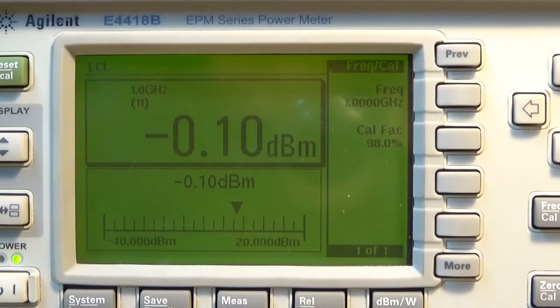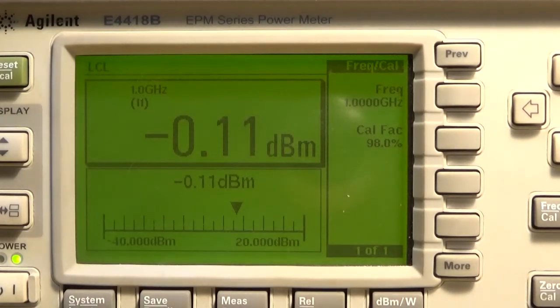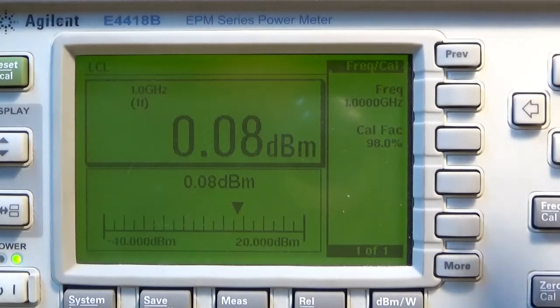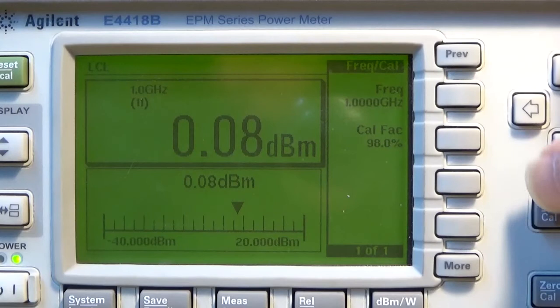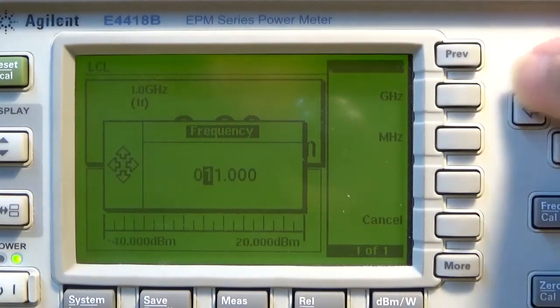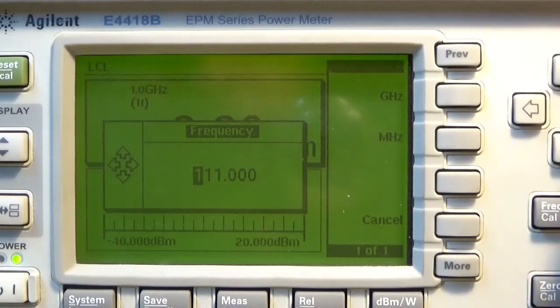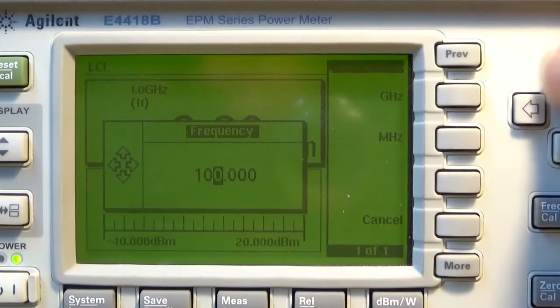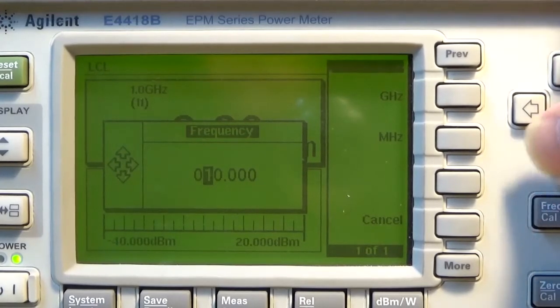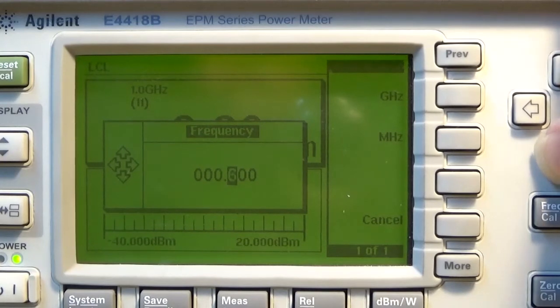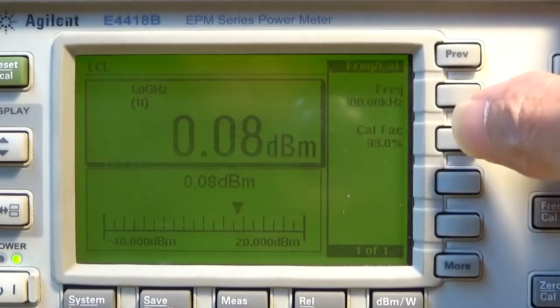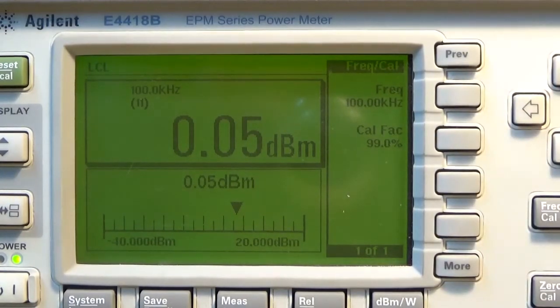I think I'll do one more test down the lower end of the scale, right down at say 100 kilohertz. Right, I'm now inputting 100 kilohertz, but of course I've got to change all this again. No, I can't do it that way because it hasn't got a kilohertz button. So I've got to go all through this to get to 100 kilohertz, which is the most annoying thing about this thing. So it's 0.1 megahertz I want. Right, now it's adjusted itself for 100 kilohertz, and as you see I'm reading almost exactly 0 dBm.